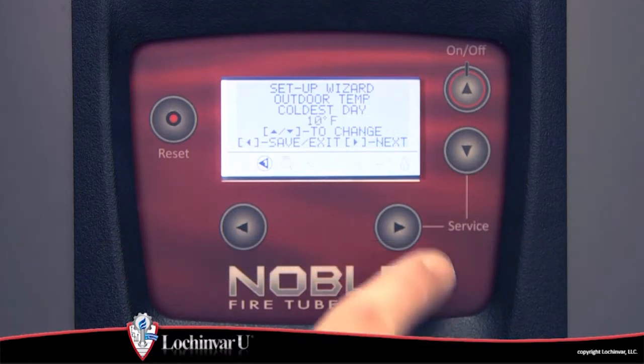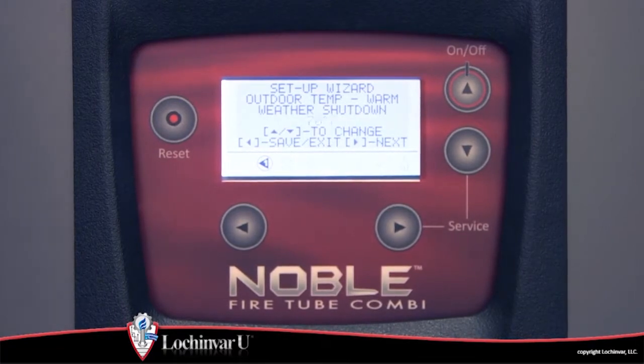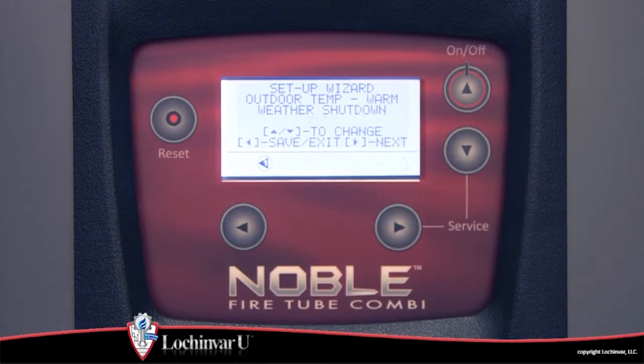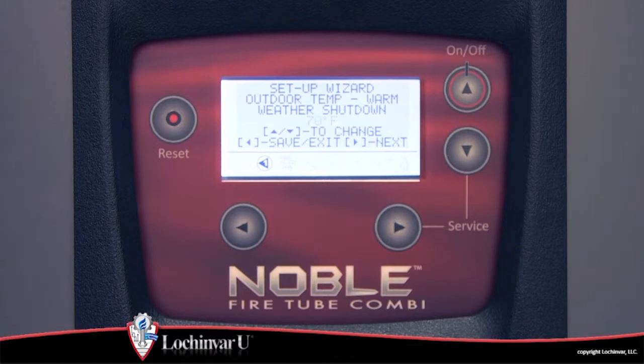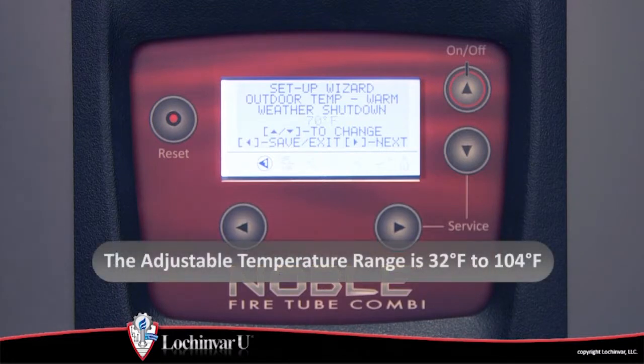The fifth parameter visible is warm weather shutdown. This parameter represents the outdoor temperature at which the control will block all space heating demands. Once the outdoor temperature falls 10 degrees Fahrenheit below this set point, space heating operation will resume. The adjustment range for this parameter is 32 degrees Fahrenheit.